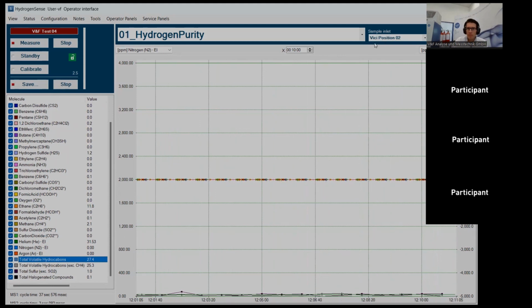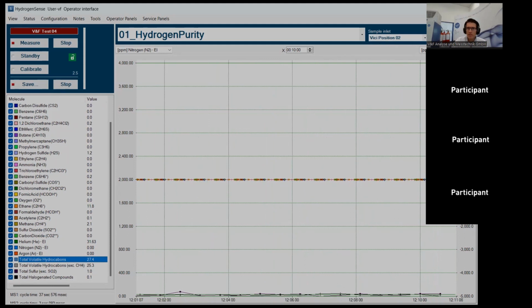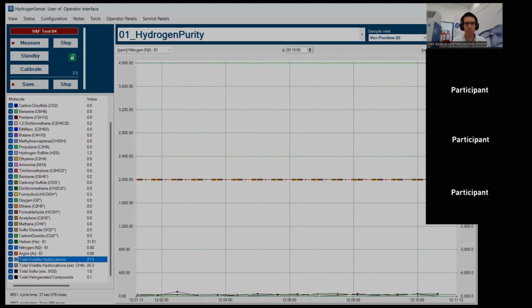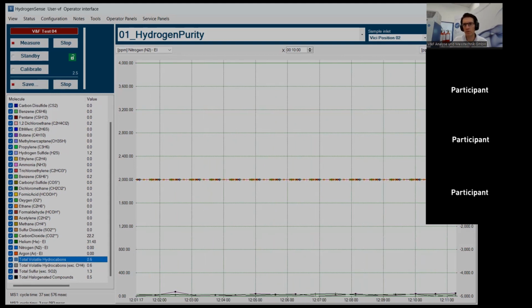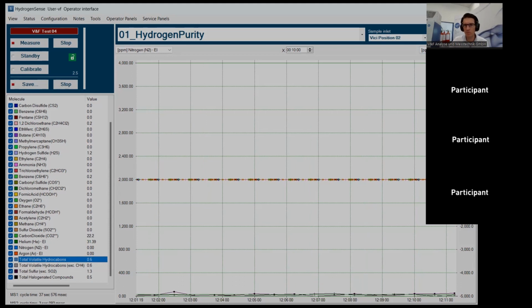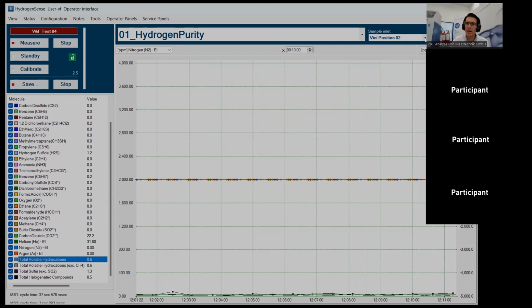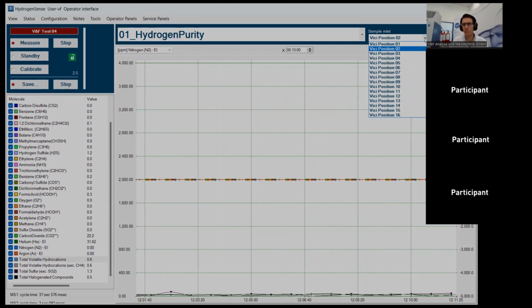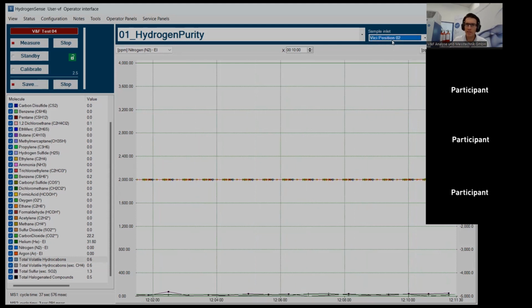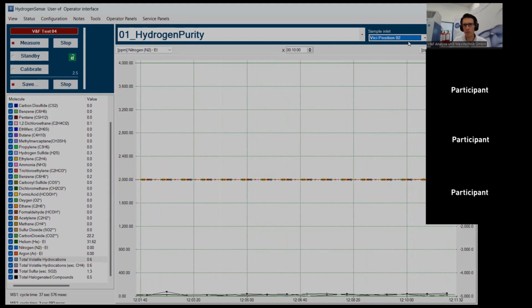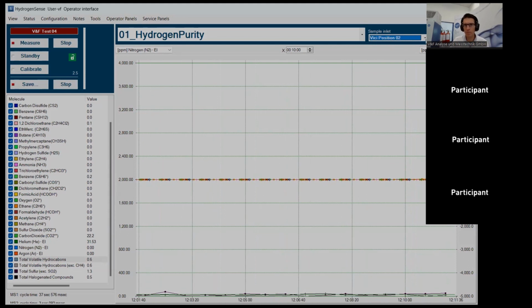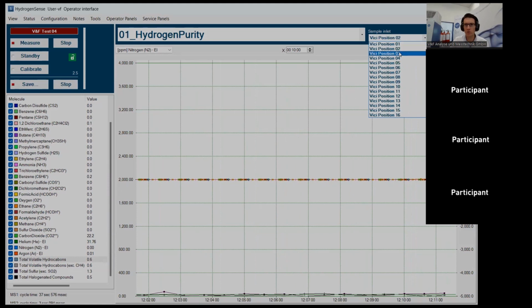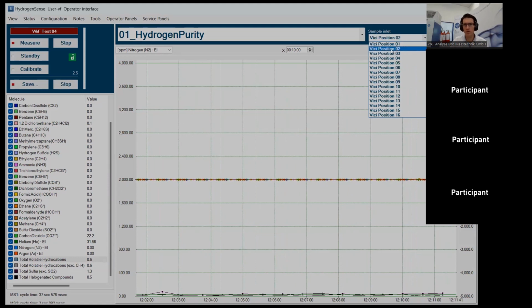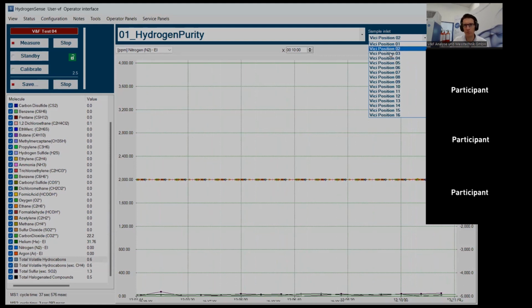Up here we see the sample inlet definitions and the sample inlet pressure. The sample inlet pressure is a rather key setting which affects the performance of the instrument. So this is something that I will not change, because it is not something that you should be able to change. And here we have all the different positions of the multiplexing valve. Once I change an inlet here, the multiplexer will go to its corresponding position. And each of these inlets is also connected to a certain flow rate setting of the mass flow controller.